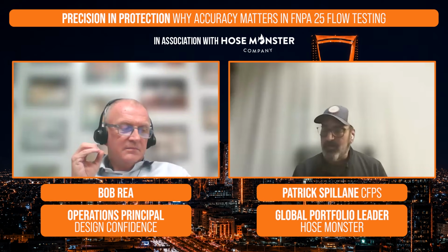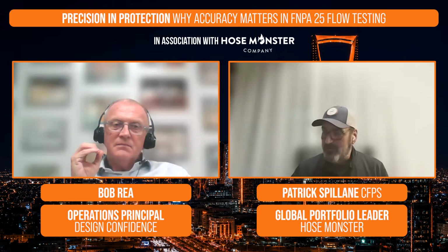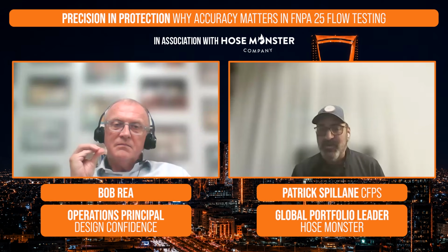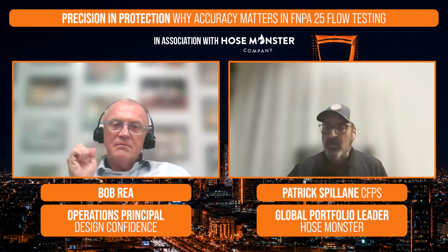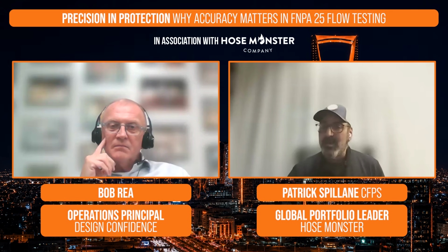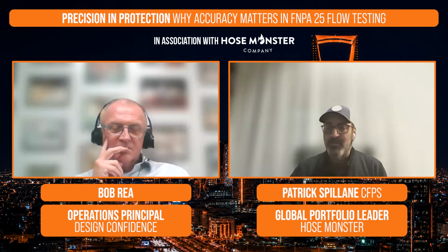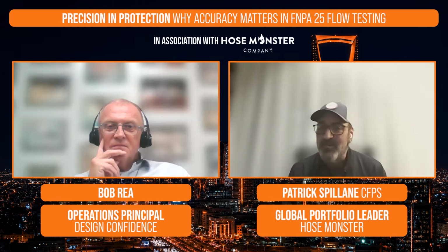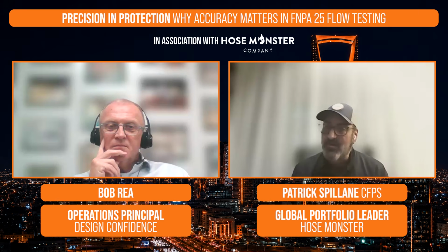A lot of times, because those flow meters are owned by the building owner and not the contractor who may be coming on site, where the contractor is going to bring his Smart Monsters or his calibrated gauges to the job site, he doesn't have a lot of control over that gauge that's owned by the building owner, but it's making sure that gauge does come out and get sent away for calibration. The whole unit, the whole flow meter doesn't need to be uninstalled. It's just the gauge itself, unhooking the hoses, taking the gauge off, and sending that in for calibration.